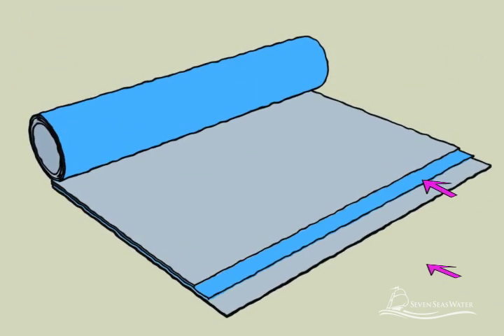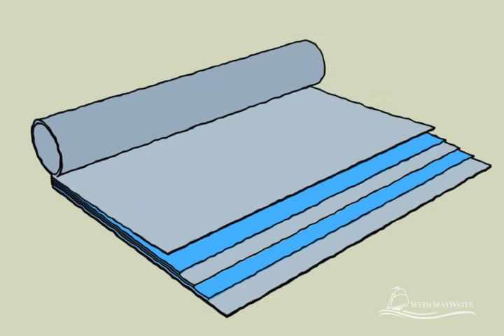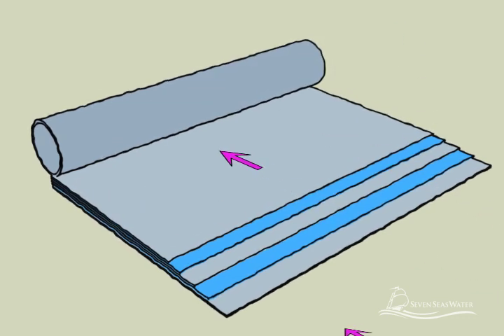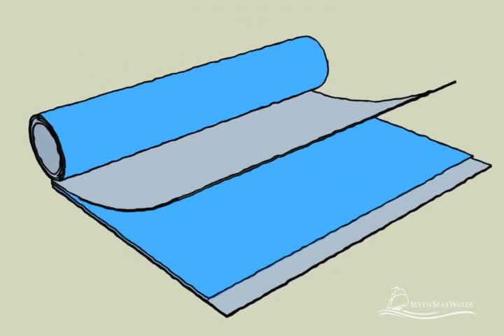The reverse osmosis membrane can be thought of as a number of sealed envelopes connected at their open ends to a tube. There are spacers between each envelope which allow water to flow across the membranes. The membrane envelopes and spacers are then wound around the tube like a roll of paper towels.